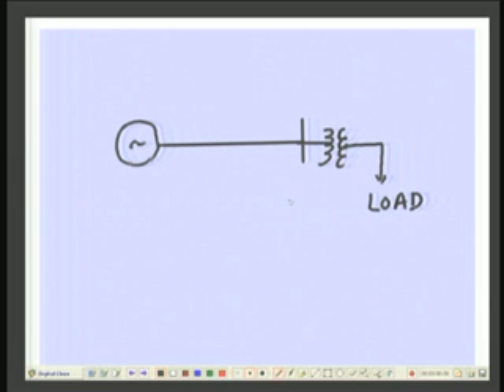This transformer is provided with an under load tap changer, right. Now, when you increase the load here, you are actually reducing the load impedance to increase the power, or otherwise you can say that we are increasing the load admittance. Now, if the voltage drops here, what is the action of this ULTC? It will try to maintain the voltage at this point. And how does it maintain the voltage? By changing the transformation ratio.